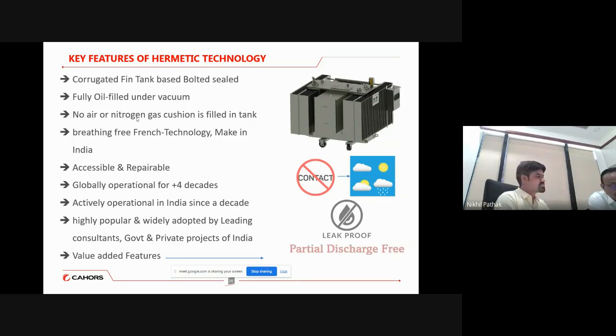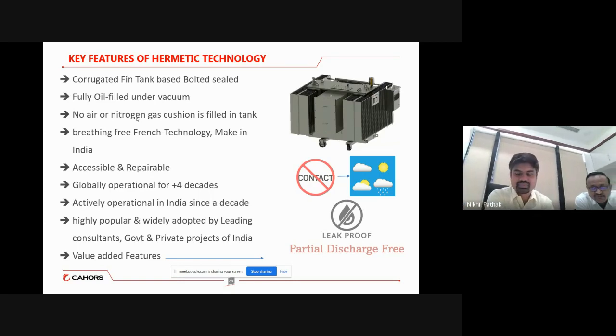Other than this, I will add one more point. What gaskets are we providing at the top cover? We provide a gasket retainer and a nitrile cord there. So even with an operational life of more than 15 or 20 years, that gasket may not be damaged because we are providing retainers on that gasket, so there will be no damage to the gasket during the operational life of the transformers. That is the major advantage of these hermetically sealed transformers, and we have not found any oil leakages from that cover point also. Yes.